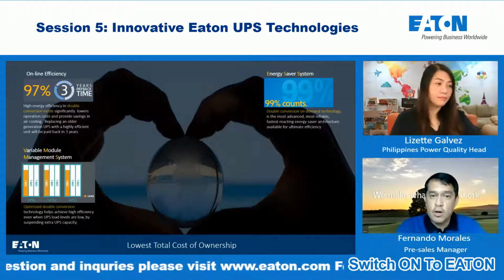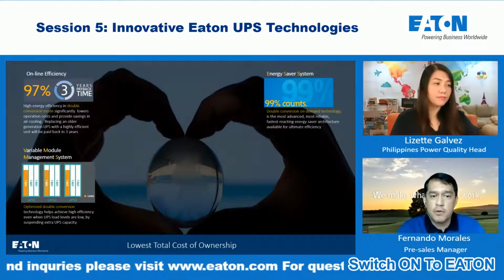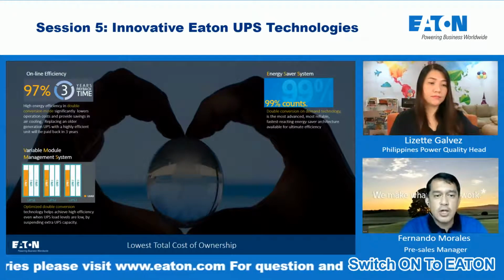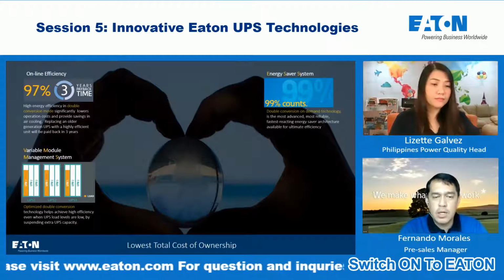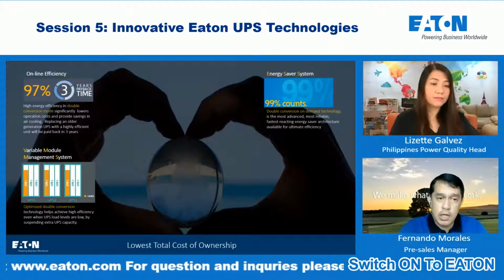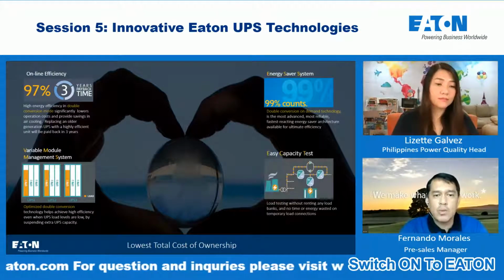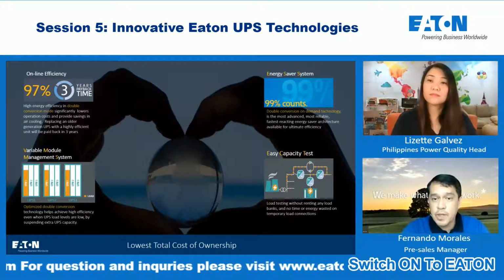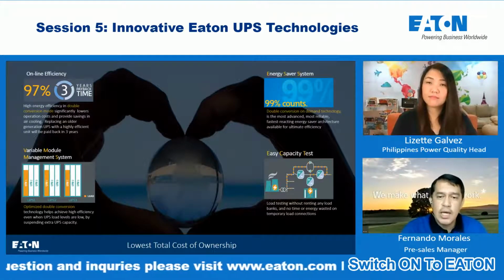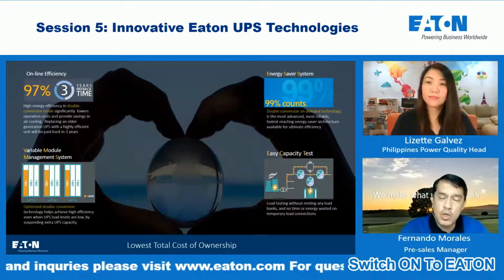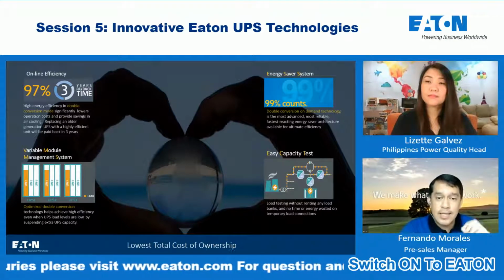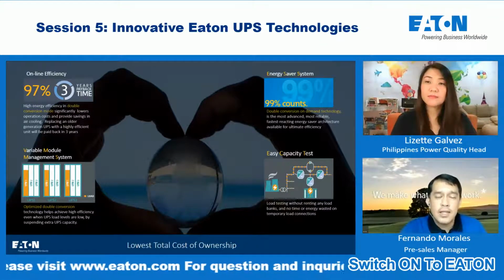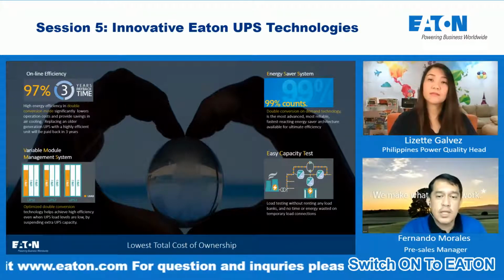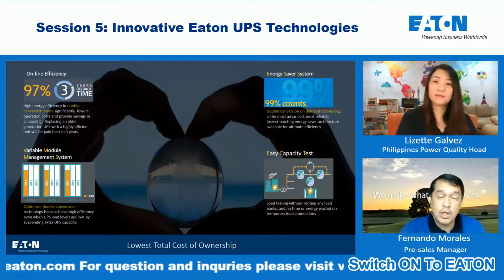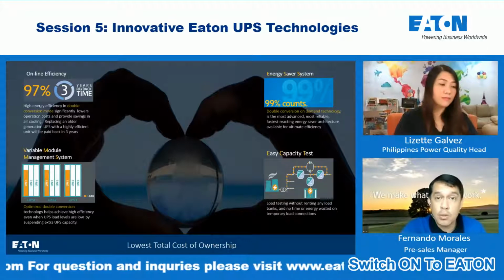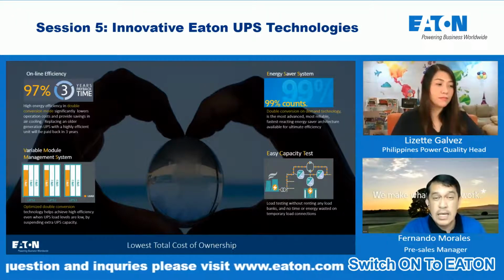That's the offering from Eaton. Another technology we've embedded on all our three-phase UPS is what we call the Easy Capacity Test, or ECT. With this technology, it enables the user to test their entire powertrain of the UPS under full load stress, without requiring an external load bank.